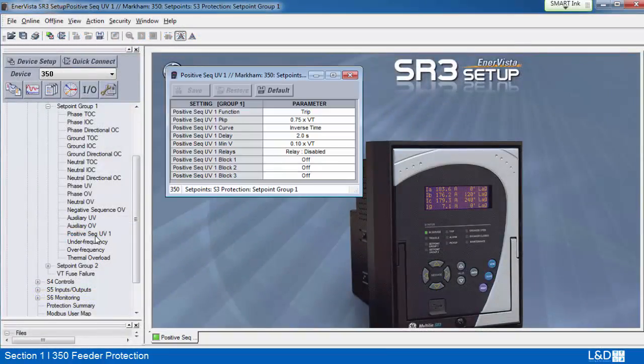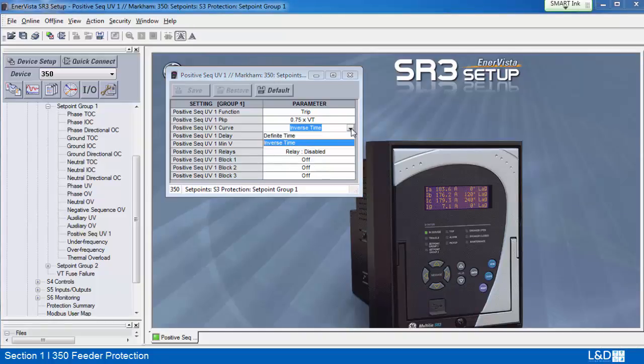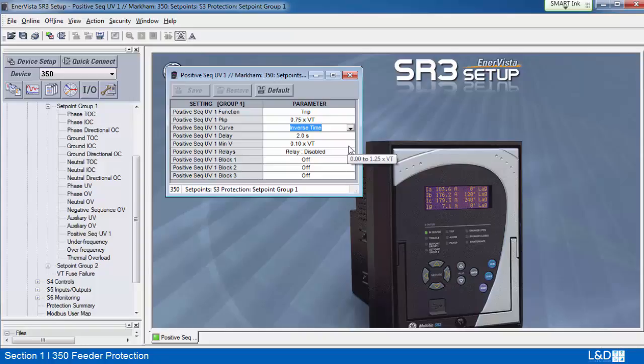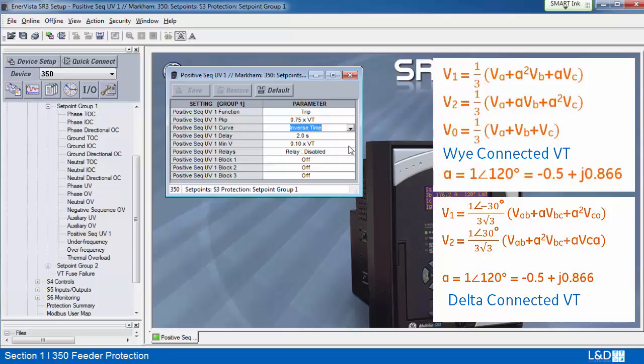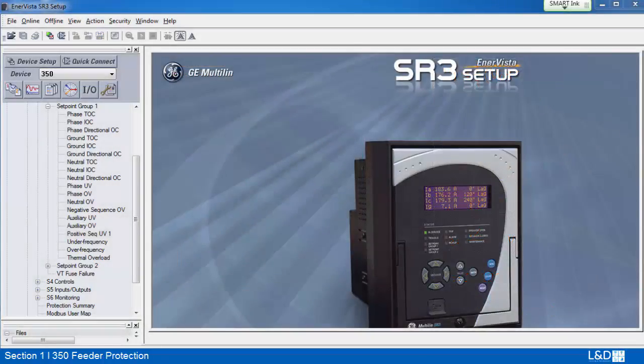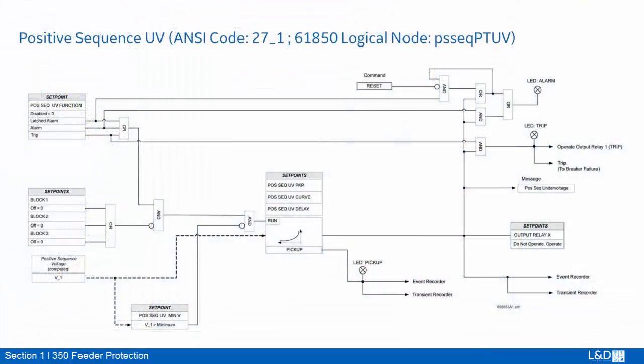Positive sequence undervoltage is a unique feature in the multilin relay series. It has the same settings as phase undervoltage, and the time delay characteristic can be programmed as either definite time delay or inverse time delay, with minimum supervision voltage levels. The difference is that the input is the calculated positive sequence voltage instead of measured three-phase voltage. Let's review the Fortescue equations for calculating positive sequence voltage. From the logic diagram, the input is calculated positive sequence voltage V1, and the minimum supervision voltage also uses V1.